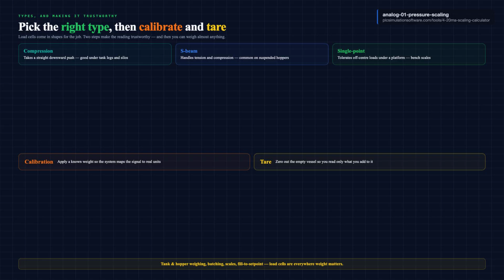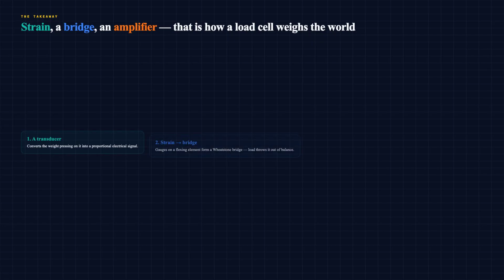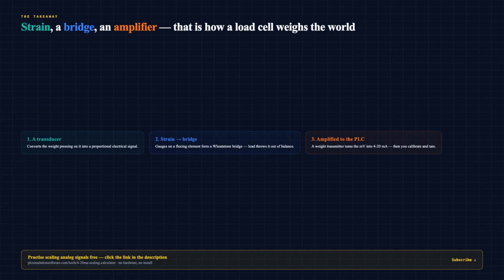So here's what to walk away with. A load cell is a transducer that turns weight into an electrical signal. Inside, strain gauges on a flexing element are wired as a Wheatstone bridge. Load throws the bridge out of balance and produces a tiny millivolt output. That output gets amplified by a weight transmitter into a 4 to 20 milliamp or digital signal your PLC can read and scale. Calibrate it, tare it, pick the right type, and you can weigh almost anything. Now, go make it concrete.